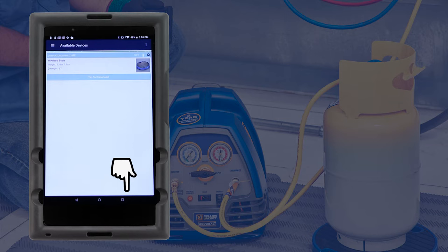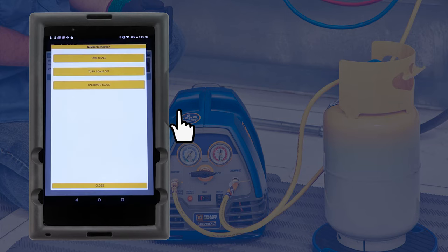Click on the gear icon above the scale image. From this screen you can tare or zero the scale, turn off the scale, or recalibrate the scale if the factory calibration is compromised. With the recovery cylinder placed on the scale, we're ready to begin recovery of this system and tare the scale.